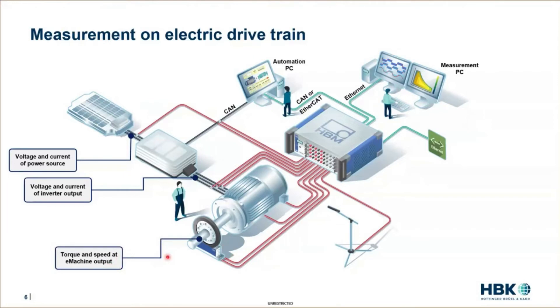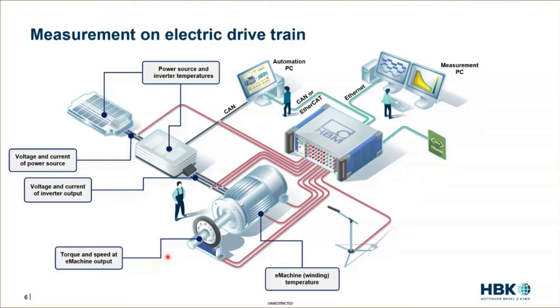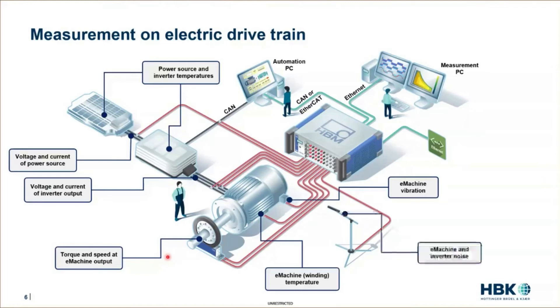Beside these electrical quantities, it is often of interest to measure temperatures — for example, the winding temperatures of the machine, or also of the inverter and the battery. Many customers are also interested in vibration measurements and acoustic noise signals. A big challenge is to collect and store all these different physical quantities as raw data, sample by sample, in order to be flexible and able to calculate further system parameters and relevant quantities that customers are interested in.